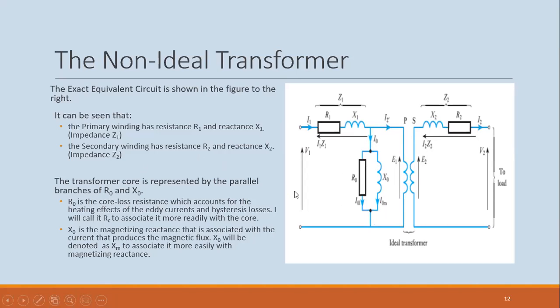Let's talk about the core. In this diagram, the core is represented by the parallel branches R0 and X0, normally called RC and XM. RC is the core loss resistance, a resistance of the core material, representing the losses due to eddy current and hysteresis.